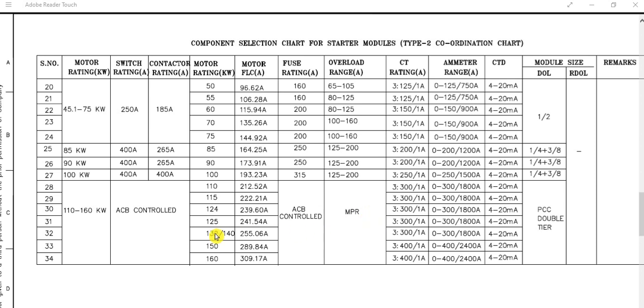That means here only ACB control and MPR, motor protection relay. There is no switch, no contactor, no fuse, and no overload range specified, because a dedicated motor protection relay will be provided separately for the motor protection. And again, this is the CT ratio, and the ammeter will be connected via CT, and this is the current transducer signal. This signal will be transmitted to the remote cabinet.